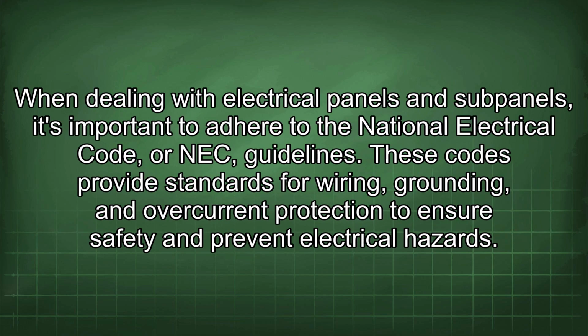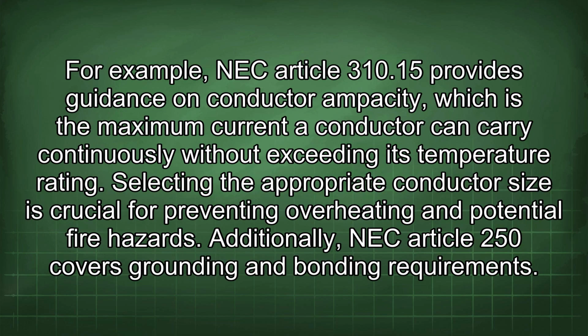When dealing with electrical panels and subpanels, it's important to adhere to the National Electrical Code, or NEC, guidelines. These codes provide standards for wiring, grounding, and overcurrent protection to ensure safety and prevent electrical hazards. For example, NEC Article 310.15 provides guidance on conductor ampacity, which is the maximum current a conductor can carry continuously without exceeding its temperature rating. Selecting the appropriate conductor size is crucial for preventing overheating and potential fire hazards.